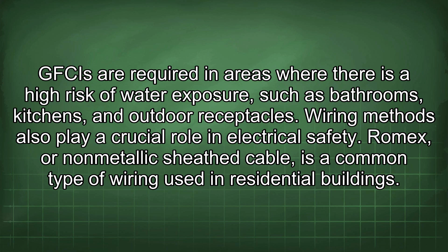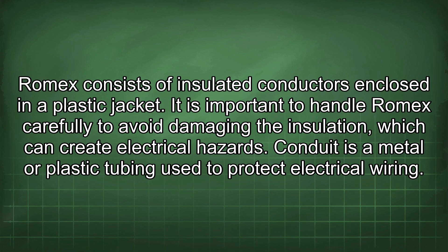Romex, or non-metallic sheath cable, is a common type of wiring used in residential buildings. Romex consists of insulated conductors enclosed in a plastic jacket. It is important to handle Romex carefully to avoid damaging the insulation, which can create electrical hazards. Conduit is a metal or plastic tubing used to protect electrical wiring. Conduit provides physical protection for the wiring and can also serve as a grounding conductor. Different types of conduit are available for different applications, such as rigid metal conduit, electrical metallic tubing, and flexible metal conduit.